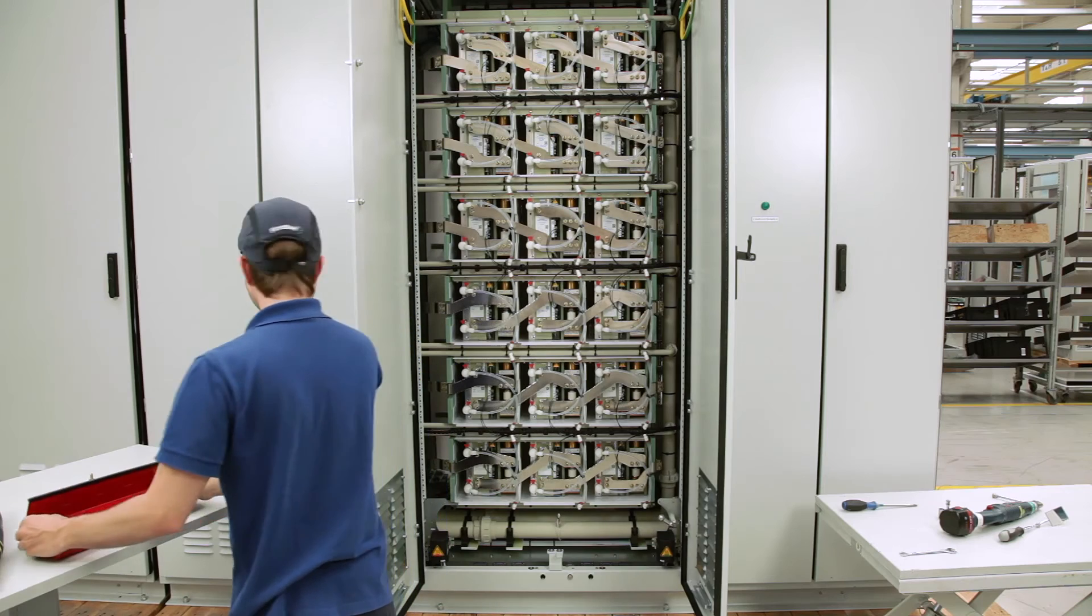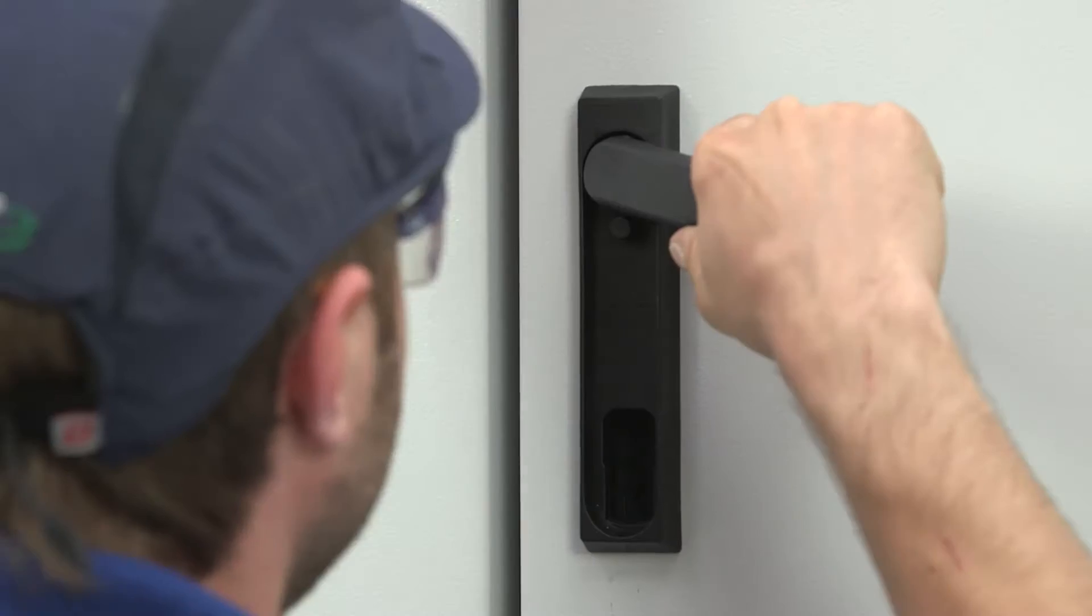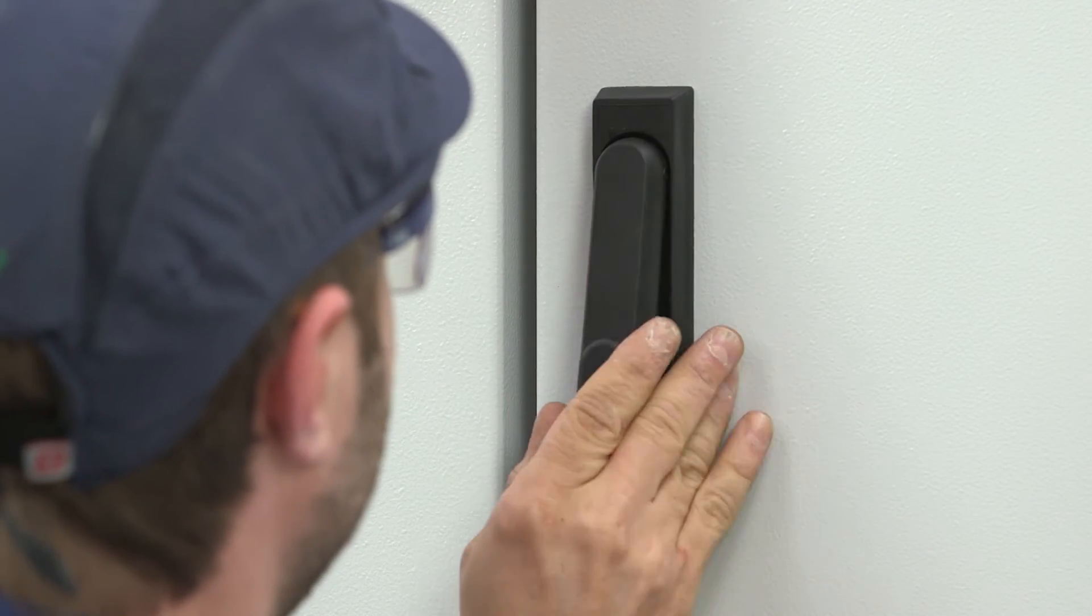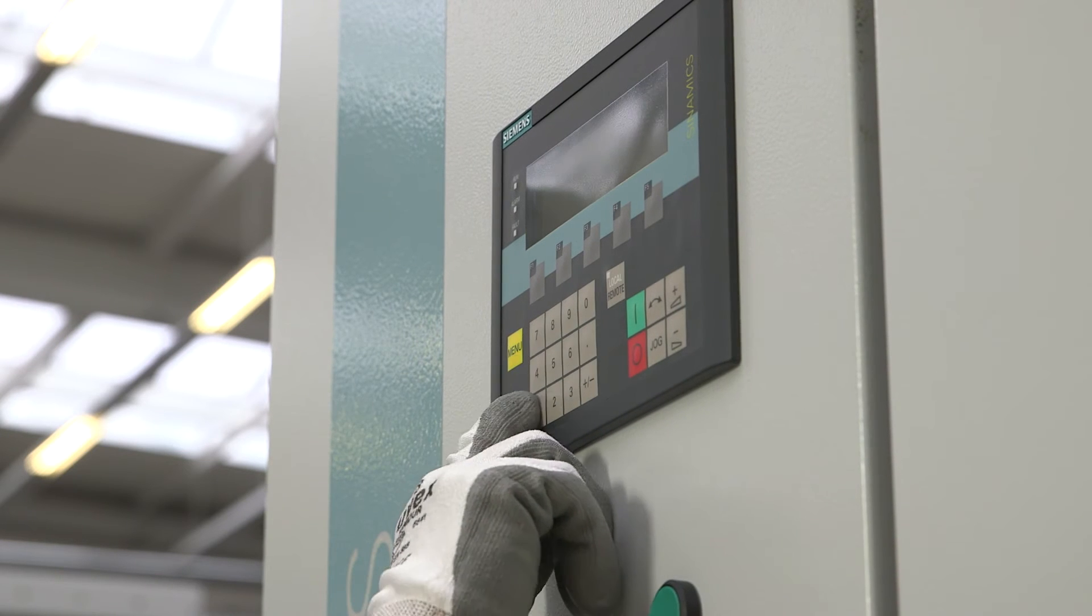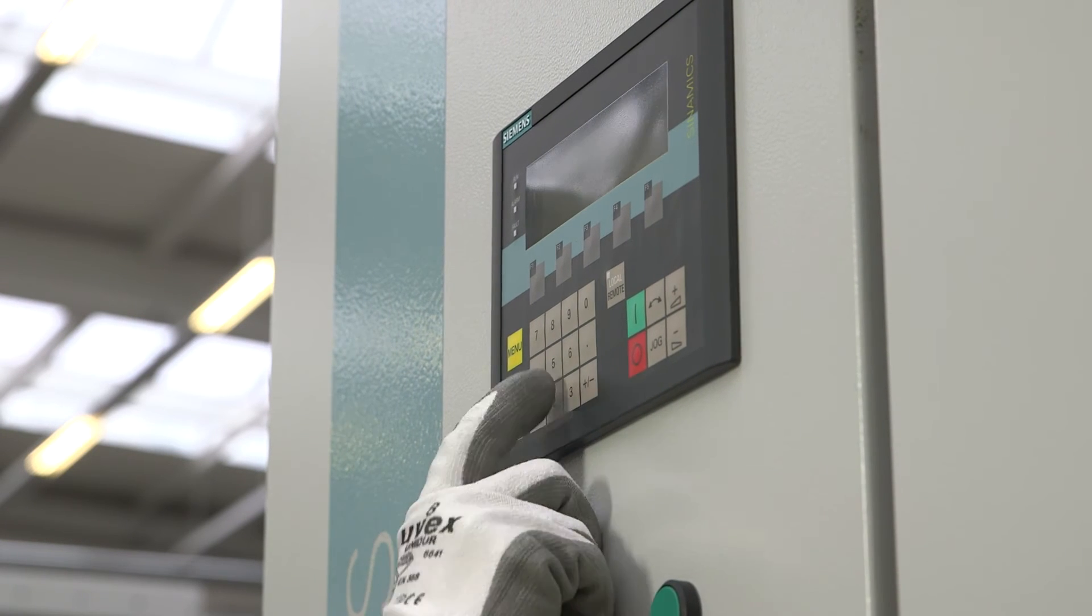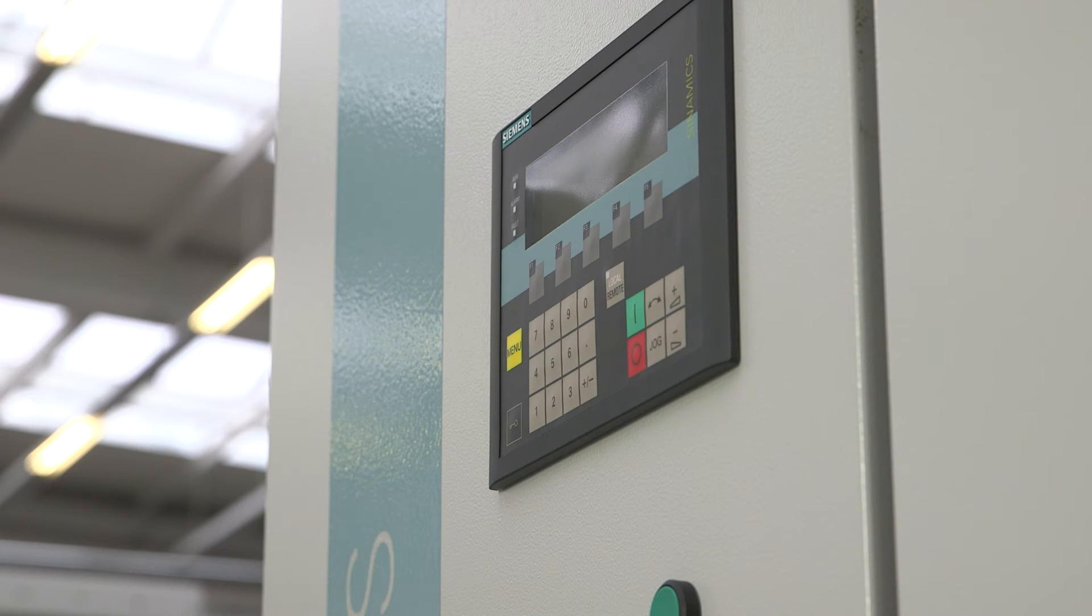Then close and lock all of the doors of the drive and switch on the auxiliary voltage again. When the bypass has been triggered, the power cell is electronically marked. After installing the new power cell and the bypass, you must reset this marking.